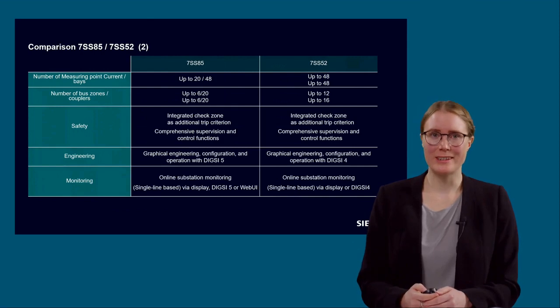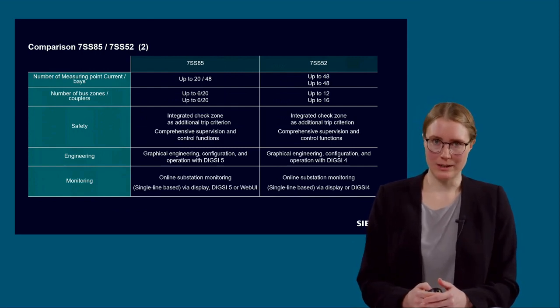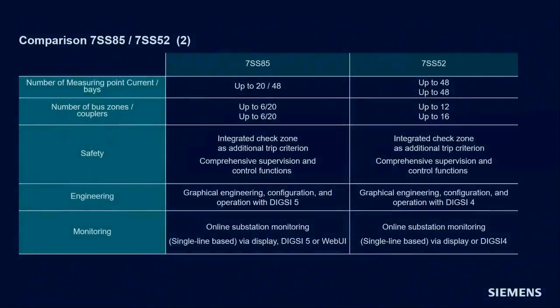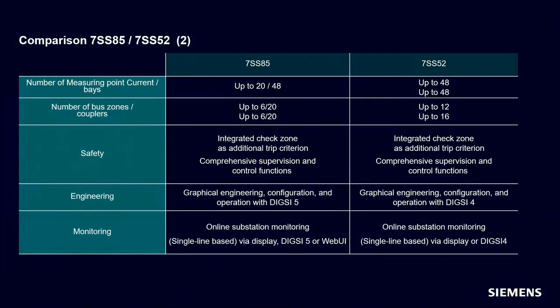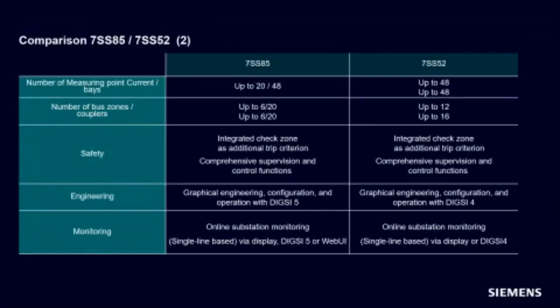For the online monitoring, we can offer for SIPROTEC 4 and SIPROTEC 5 a single line based view via display or DIGSI 5. Here you can check the current values, the differential values for each zone, and the disconnector image with the status of all disconnectors. For the 7SS85, there's additionally the web browser available.